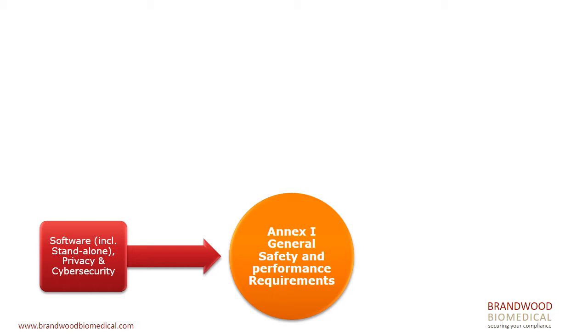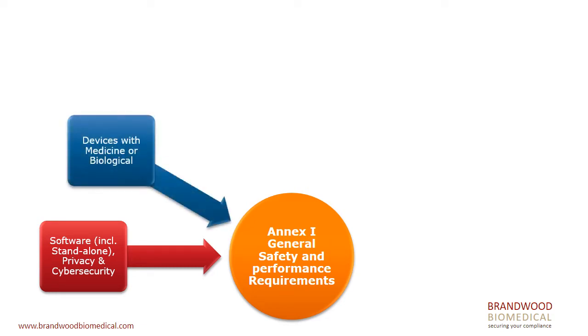But in addition to that, there is content in the essential safety and performance requirements on privacy and cybersecurity. So that now raises its head in the regulations for the first time, and you are now required to comply with appropriate European privacy regulations if you have software which, for example, contains patient identifying information, and your devices need to be appropriately designed for cybersecurity to prevent interference or malfeasance. So, new approaches to software.